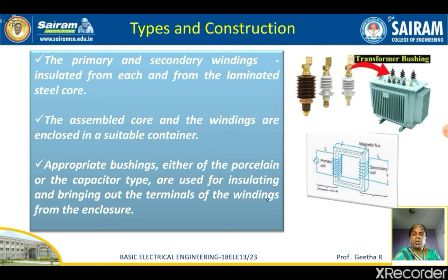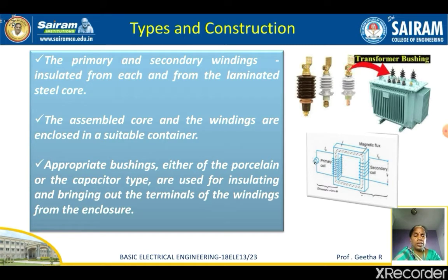Now we will look at the different types of transformers and their construction details. The primary and secondary windings are insulated from each other and also from the laminated steel core. The vertical portions of the core are called limbs and the horizontal portions are called the yoke. The primary coil is wound on one limb and the secondary coil on the other, both insulated from each other and from the core. The assembled core and windings are enclosed in a suitable container, with bushings used to bring out the terminals.